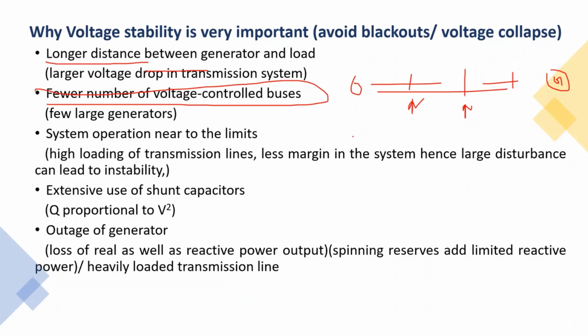So you know that there are a very large number of substations, but generating stations are limited, and FACTS devices are limited. That's why it is very important that during voltage stability assessment we consider how many voltage control buses are in our control, because for those substations and generating plants, you can ask them to control the voltages, to absorb or inject reactive power.